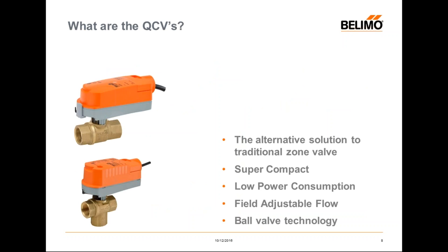The QCV is your alternative to a traditional flapper zone valve. It's super-compact and consumes less power — the traditional zone valve uses about seven watts, while the QCV, depending on your actuator combination, could be as low as 0.3 watts. The CVs are field-adjustable by removing the gray clip on the actuator and setting it to a different position that limits the rotation of the actuator, which changes the CV value.